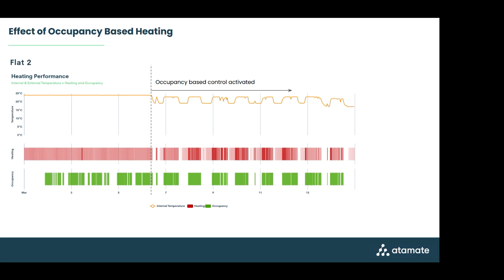If we add a little bit of sophistication, we come back onto our wall sensor unit, and now we can have three set points in a room. This is particularly relevant in older buildings - in newer build buildings it's not so relevant generally, I'll come back to that in a minute. But in older buildings, you'd have a setback point because you probably don't want to let the temperature drop totally, as it might drop too far, you might end up with condensation problems, and it might take too long to reheat.